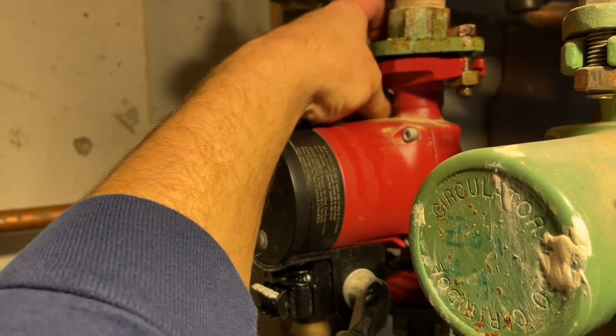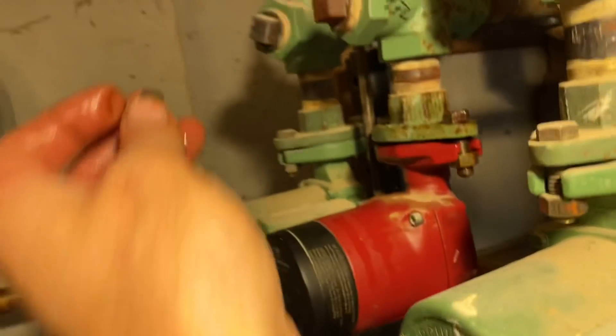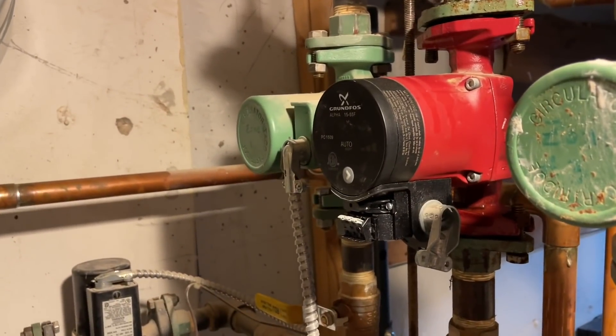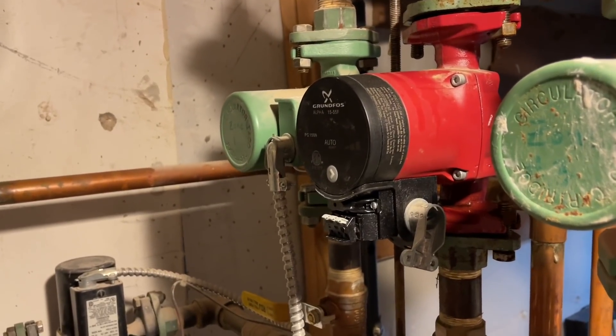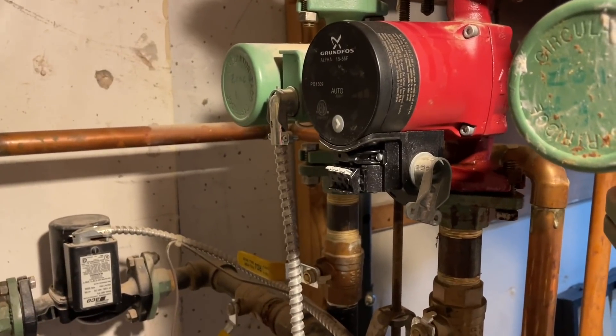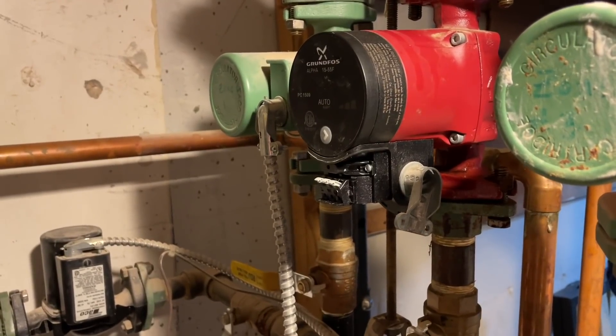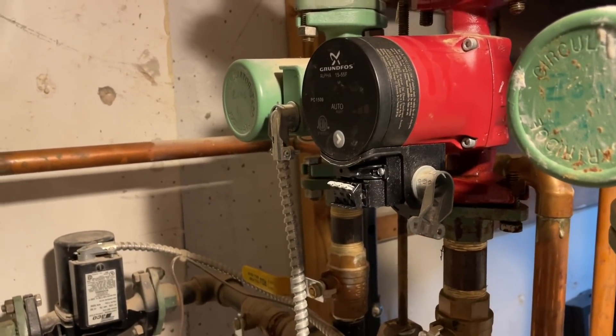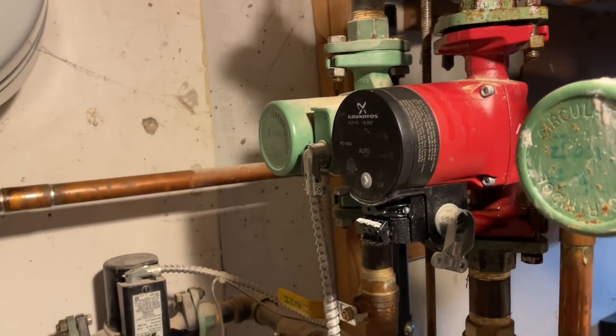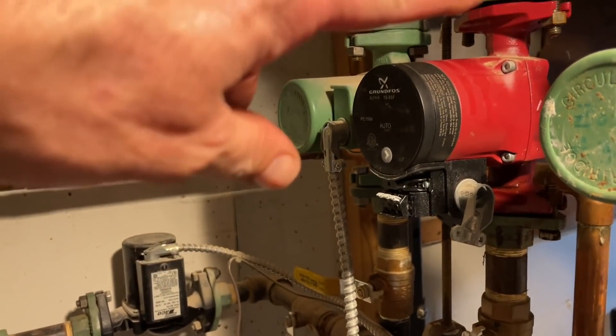She said the red one — the Grundfos Alpha circulator — they don't make them anymore because of the failures. I've probably put in... I remember one winter I was doing a brand new four-zone boiler and this is what the customer wanted, and every single one was dead out of the box. Because it tells you gallons per minute, and every single one had zero, or it would be dash-dash-dash.